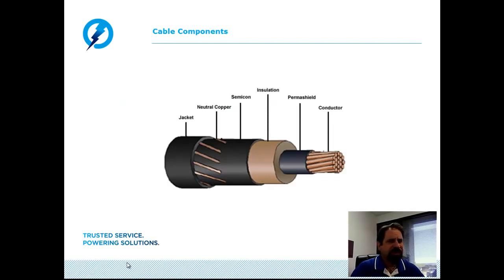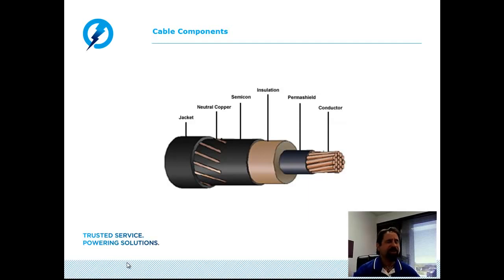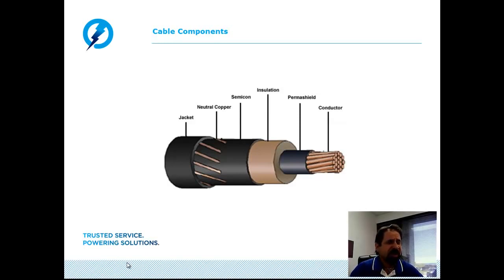Before we get started, let's talk a little bit about cables in general. The power cable market can be segmented into three areas based upon voltage class: the medium voltage class, typically 6 kV up through 69 kV; the high voltage class, typically 69 kV up through 150 kV; and the extra high voltage class, greater than 150 kV. The medium voltage cable dominates the underground cable market, used for transmission and distribution of electricity in industrial, commercial, and underground applications.